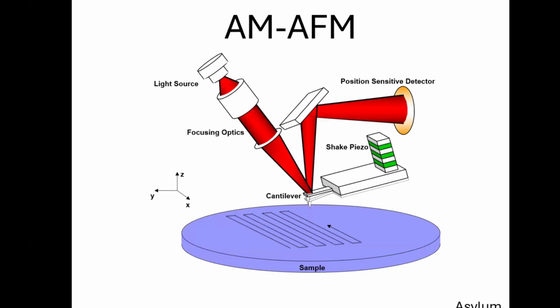Whereas the thermal noise measurement was just recording the natural state of the lever, now we want to drive the lever vibrations. We do this most commonly using a piezoelectric element close to the probe. When we apply an AC signal to the probe, the lever and tip oscillate at the same frequency.